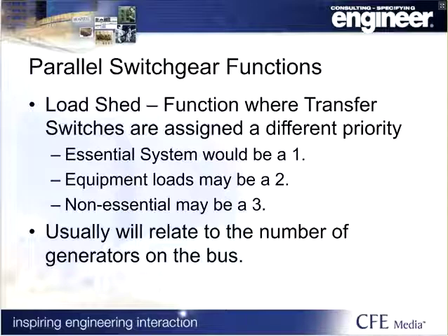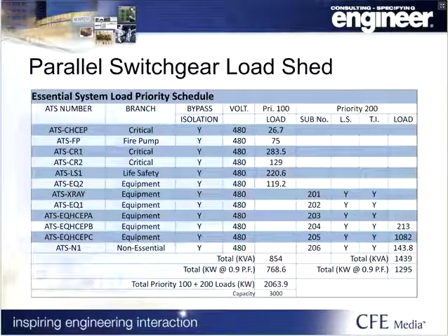So usually the number of steps in load shedding relates to the number of generators that you have. If you had a 6-generator system, you might have 6 steps. If you have a 2-generator system, it would only be 2. This is kind of an example of a system that has 2 generators.